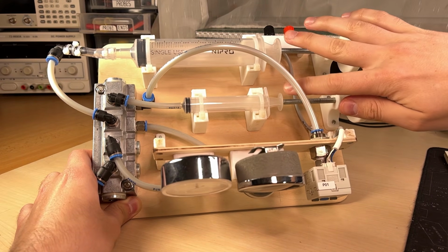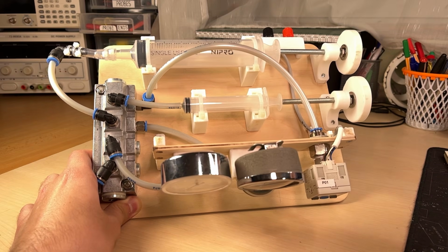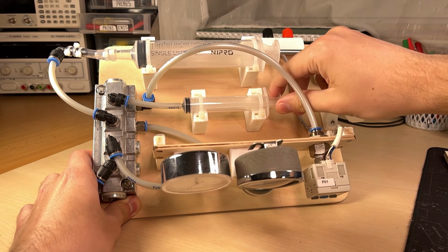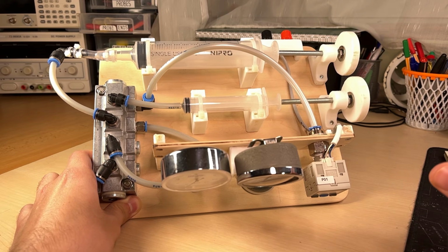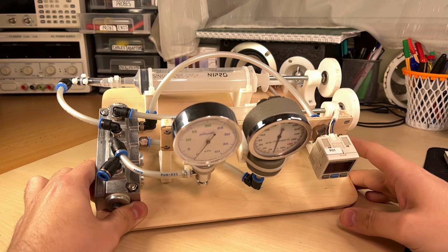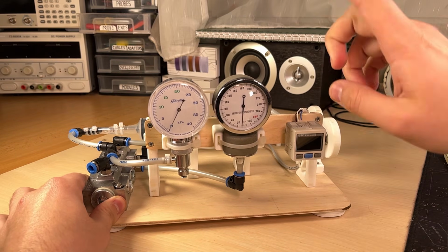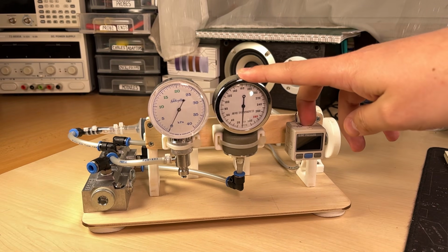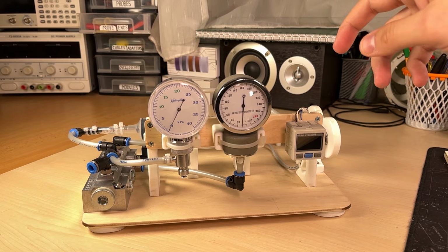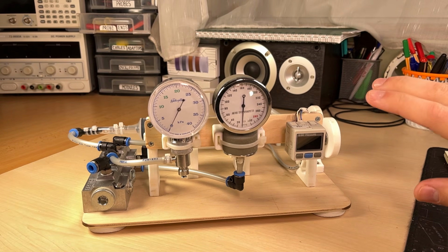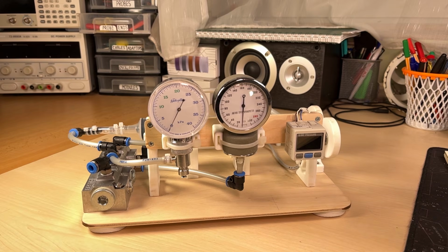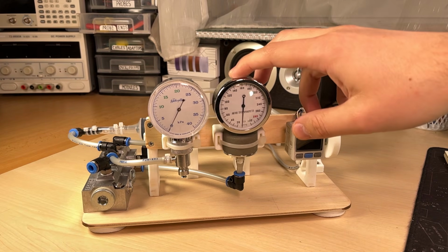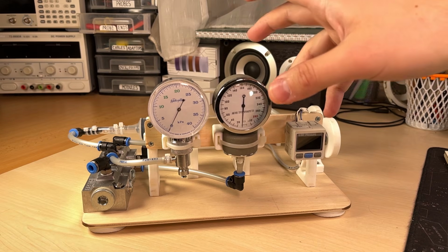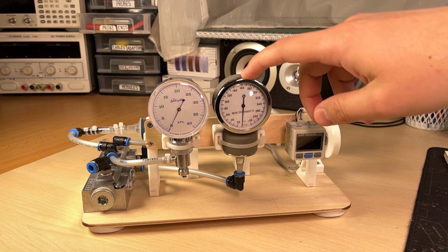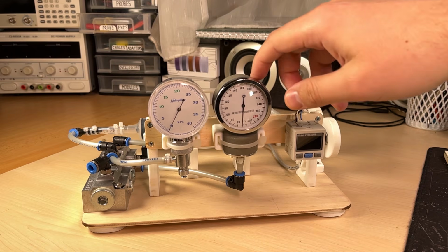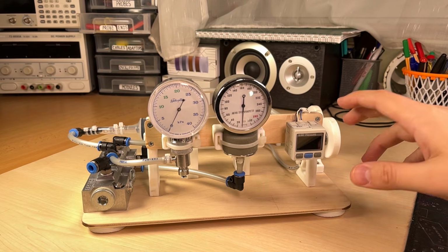There are two sizes of syringes, the bigger one so you can increase the pressure more rapidly, and the smaller one for doing smaller increments when increasing or decreasing the pressure, as you will see soon. And one more thing, I have 3 pressure sensors here just because I had them lying around, and in this way, if one of them is not correct, I can see it by the other two being close. This is what actually happened here. This one in the middle, while I thought it was really good and used it from the beginning, turned out it wasn't showing good values compared to these two.